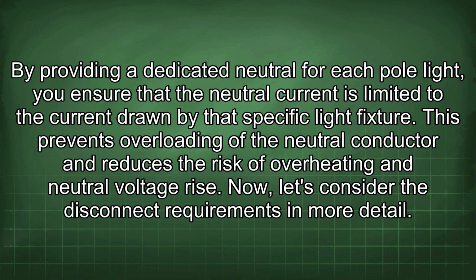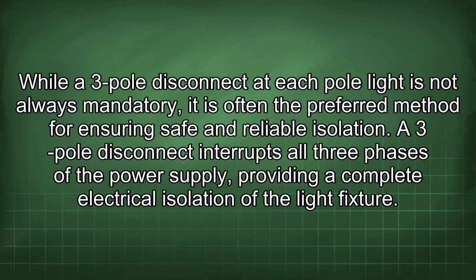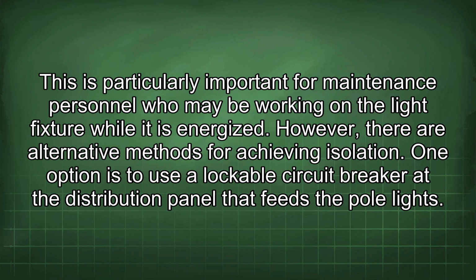Now let's consider the disconnect requirements in more detail. While a 3-pole disconnect at each pole light is not always mandatory, it is often the preferred method for ensuring safe and reliable isolation. A 3-pole disconnect interrupts all 3 phases of the power supply, providing a complete electrical isolation of the light fixture. This is particularly important for maintenance personnel who may be working on a light fixture while it is energized. However, there are alternative methods for achieving isolation.